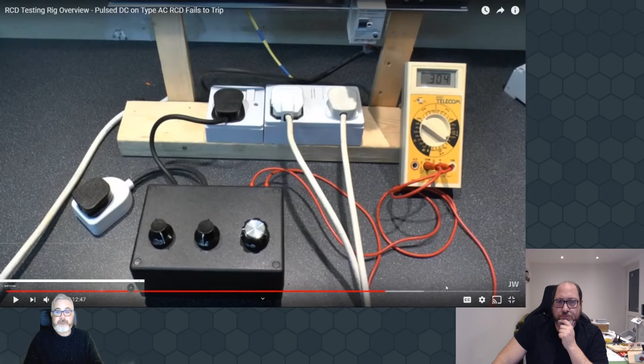So this was a rig that John Ward built. John Ward loves to experiment, melt stuff, blow stuff up. This was a very simple DC injection rig, using a simple diode like you'd find in a domestic iron. What he did was successfully stun, blind, shock and saturate the RCD so it didn't perform within the 300 millisecond or 40 millisecond performance criteria. From the snapshot of the video, it's a 30 milliamp RCD, but it's pulling 0.3 amps, so that's 300 milliamp at the time - definitely not behaving, that one.